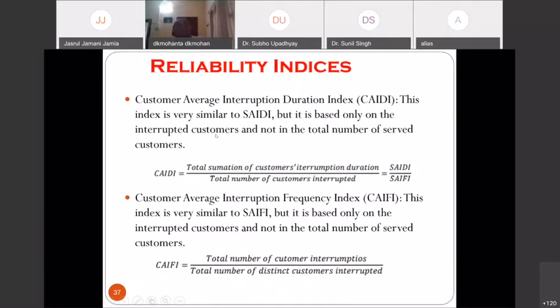Let's say we have 1,000 customers, out of which only 10 have been interrupted, others were not. We are only interested in those customers whose power supply was interrupted. So it's the total summation of customer interruption duration divided by the total number of customers interrupted, not the whole total of customers. Basically, it is a measure similar to SAIDI, that is CAIDI.